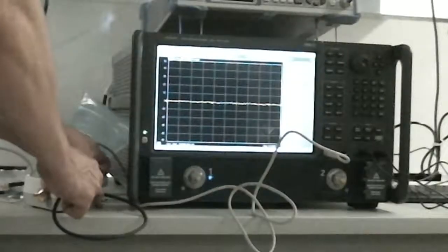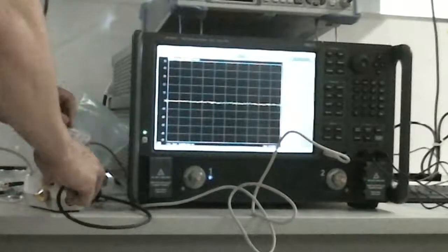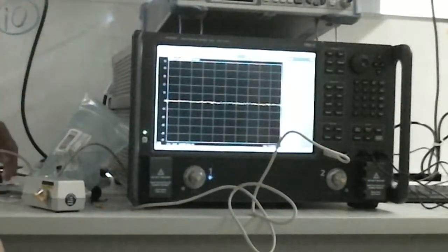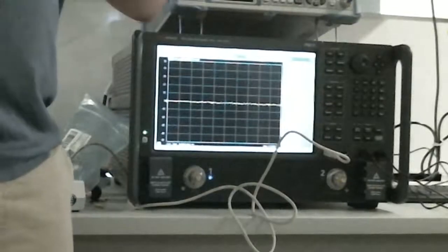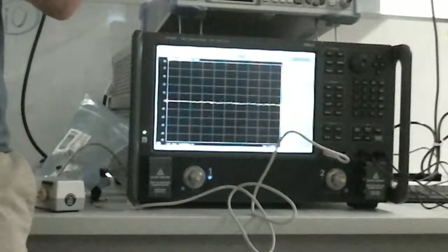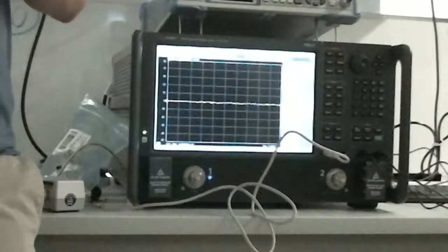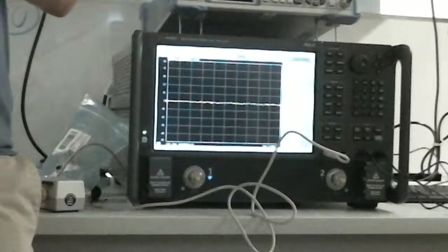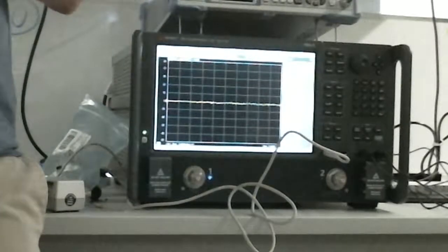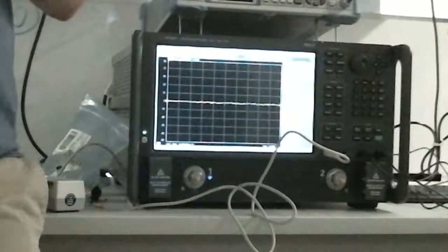I have two questions regarding the calibration. If we change the power level or the frequency span after the calibration, we have to recalibrate? So if you change the IF bandwidth, the power level, the frequency span is an exception. I'll talk a little bit about how that works. But if you change either of those two, you should not have to redo your calibration. And I'll show you how that works.